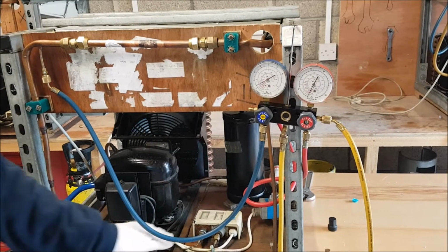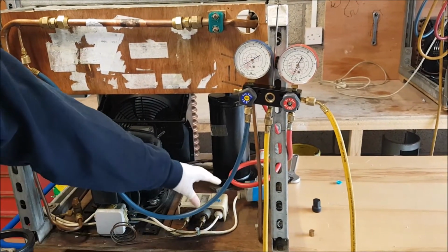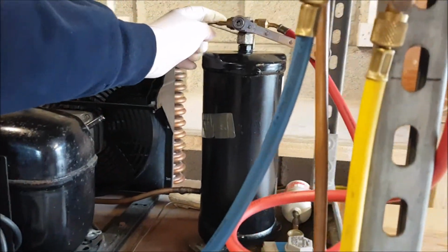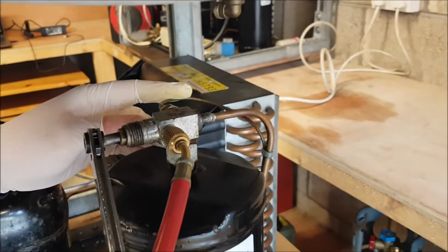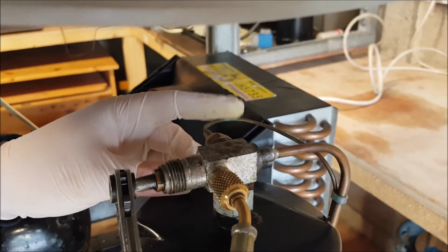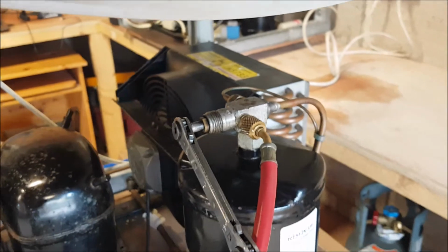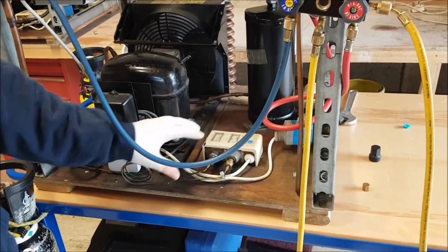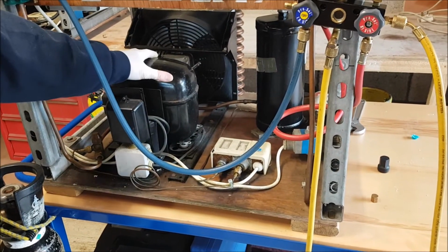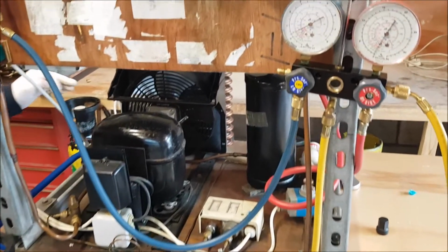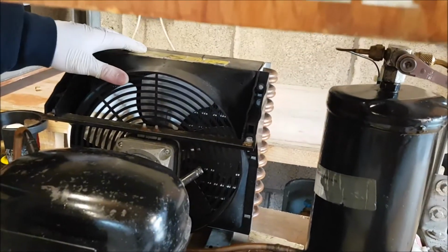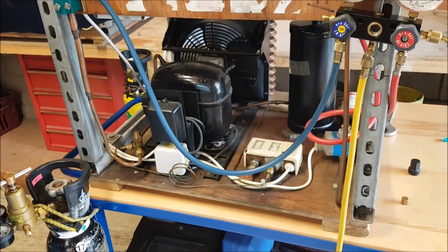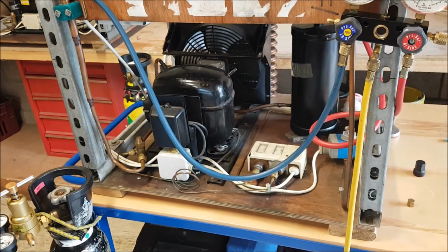It could have been as simple as just replacing this pressure switch, for example, this dual pressure switch, because remember, with the capillary line where it's located, we couldn't change that capillary or open that capillary without losing refrigerant. So if this capillary line or the pressure switch needed to be replaced, that would force us to recover all the refrigerant. Or some other repair, like on the discharge side of the compressor, or repairs on the condenser, like welding up a burst pipe on the condenser. So we had to do some kind of repairs that forced us to remove the refrigerant.